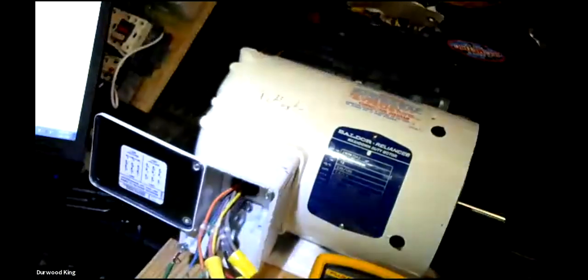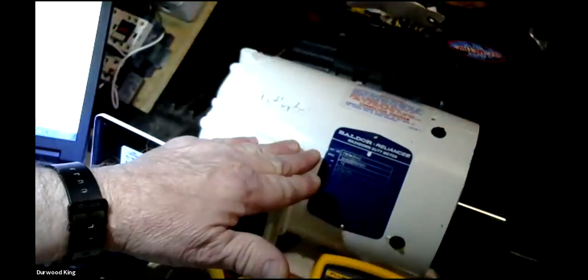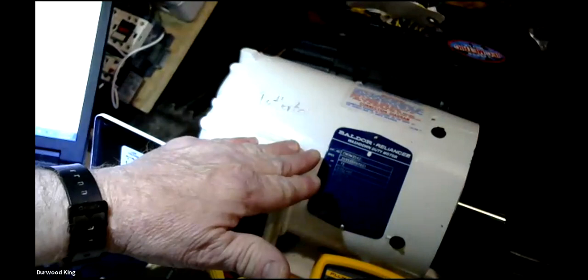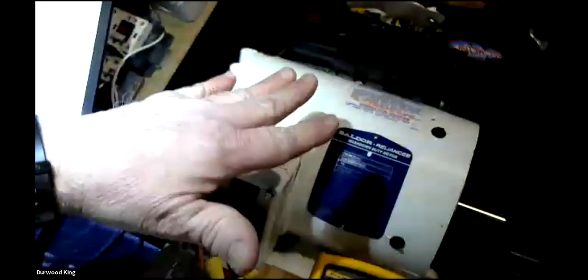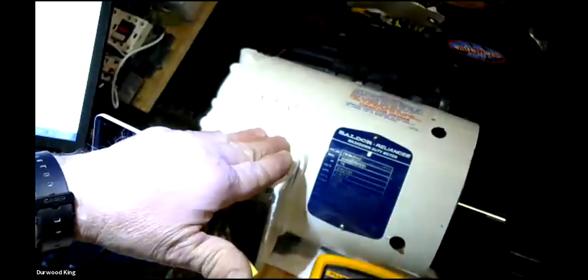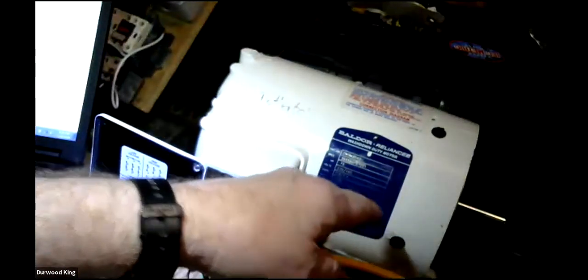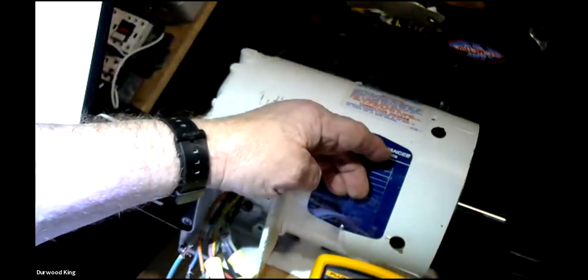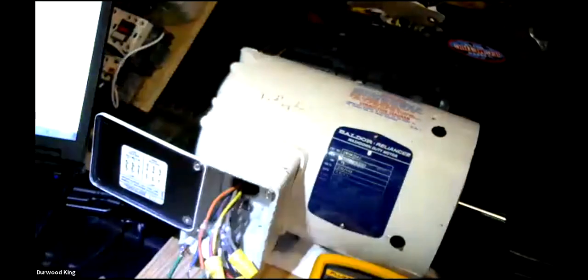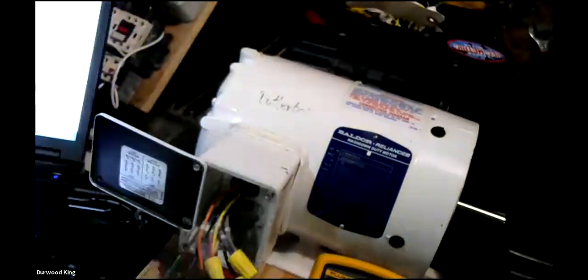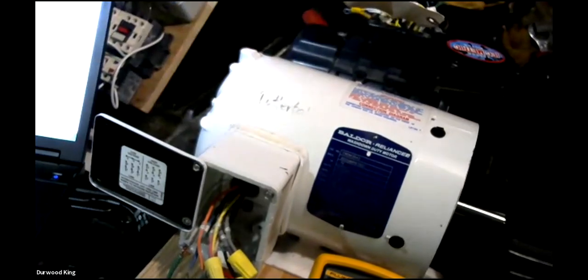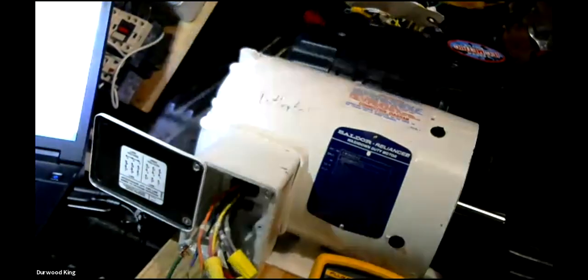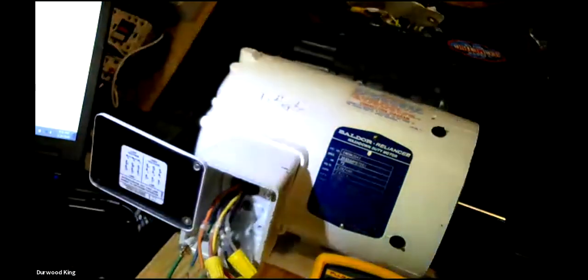delta wound. Now, when we installed that compressor down there, me and my class, about a year, well, close to 2 years ago, it had to be wired 240 3 phase, and it came in already pre-wired that way. We just tied the main power in, and when I saw that on the nameplate, I took pictures of it, and I'm trying to remember. I don't know right where they are on my computer, whether I've even got them in this computer or not. But let's see. But you saw what I just showed you, and that shows you that it actually is two deltas in parallel when you go low voltage, and it's one delta when it's in series.